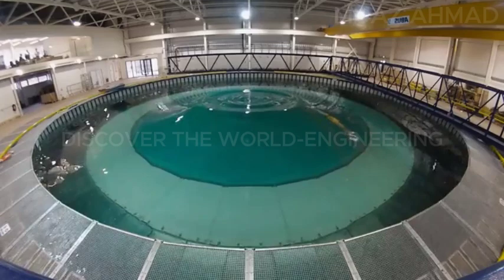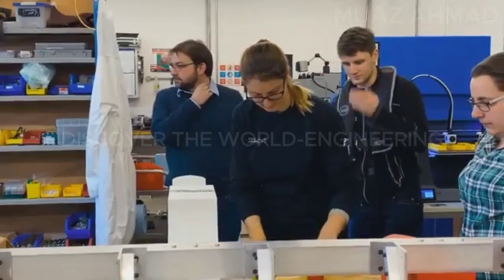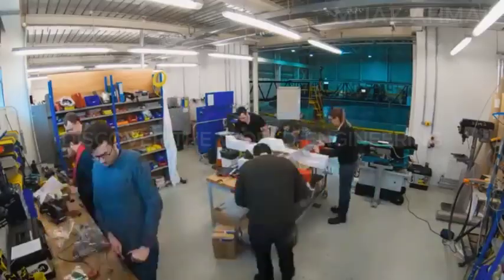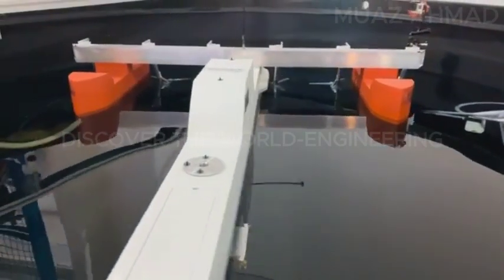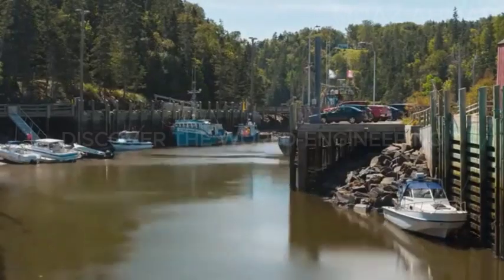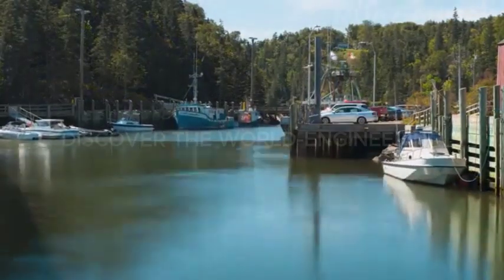But as the pumps reached full speed, something was not right. Sometimes things don't go quite as you're expecting, and this happened quite unexpectedly, that we had a mooring line suddenly break on us as we were operating at the fastest flow. The team rushed to find out what went wrong, and the answer was soon clear. It was not through engineering or design, it was completely through me putting the models together slightly wrong, so I apologize for that to the team, but it was a really interesting thing to learn from because we saw exactly what happened to the platform, where did it go, how did it move in the tank, and actually, even though we lost one mooring line, the platform worked perfectly fine, it coped.